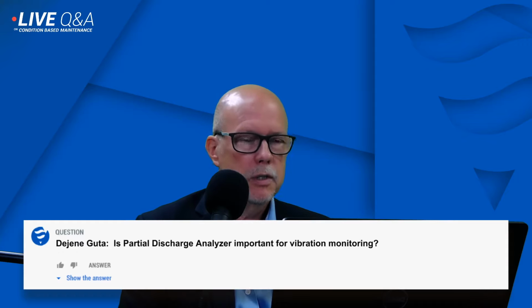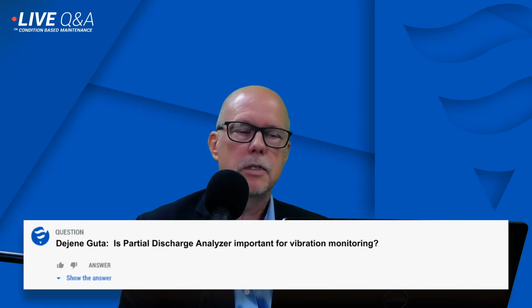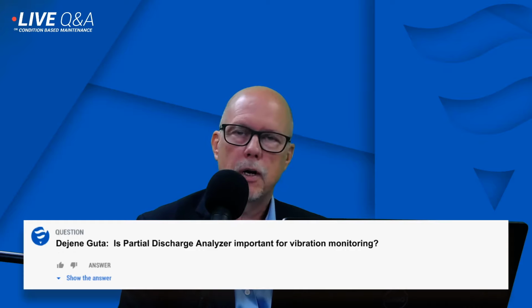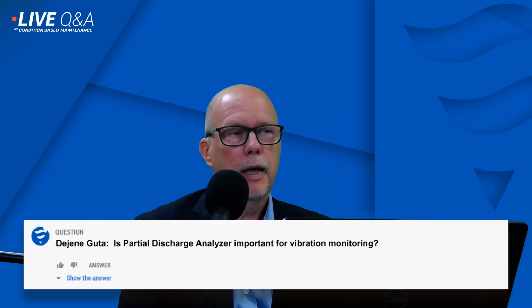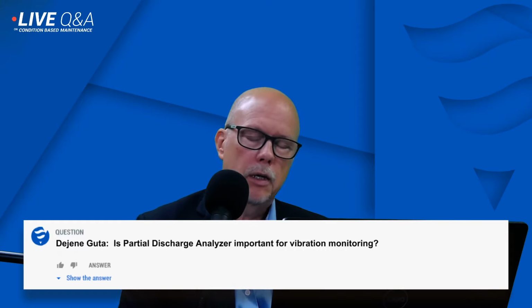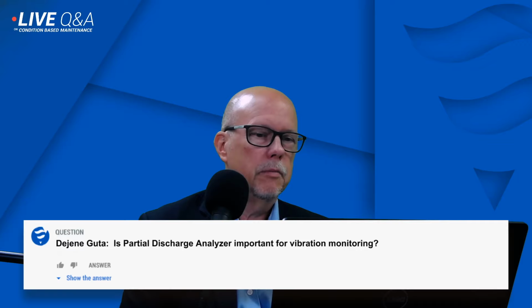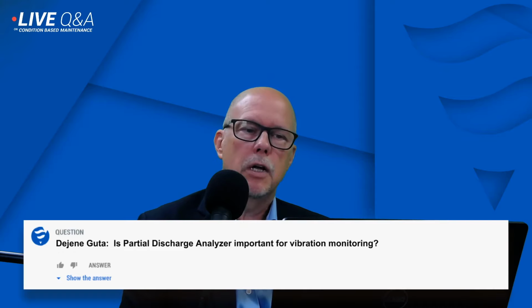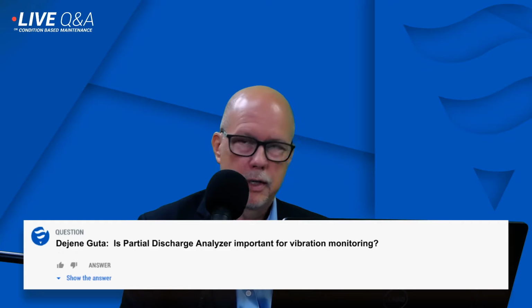If you're measuring slot discharge and you're deducing that there's vibration, in many cases, if you're at that point, it means that damage has already occurred. The objective from our point of view is to measure the vibration and be able to go in there and apply corrective measures to prevent the bars from vibrating, making them tighter in the slot so they don't vibrate, so that you never get to a point where you start seeing high PD values. So again, high PD values, I've heard this comment before. Well, we can see some slot discharge which is due to vibration, and that's true.